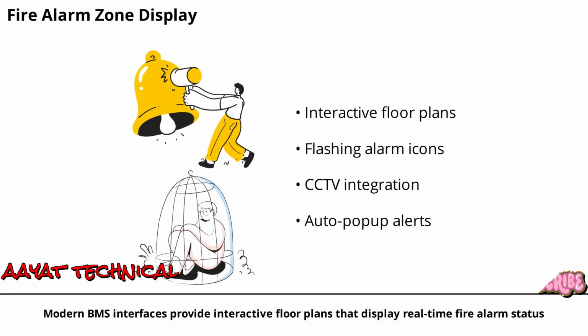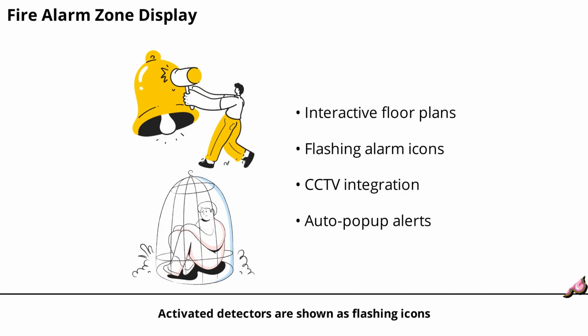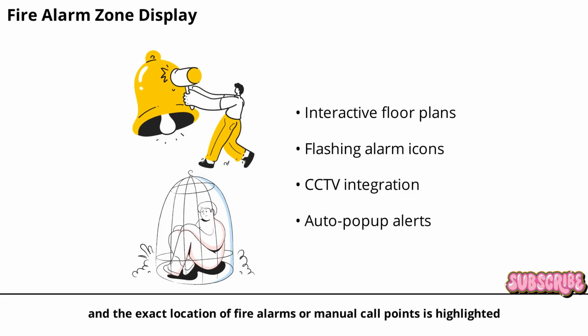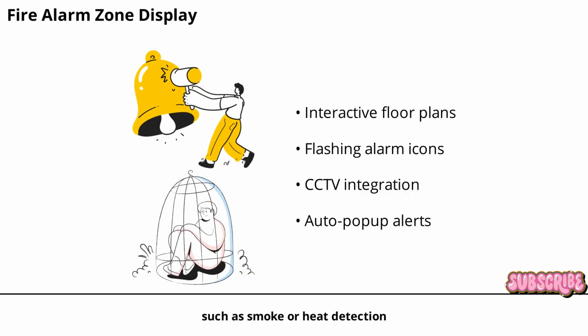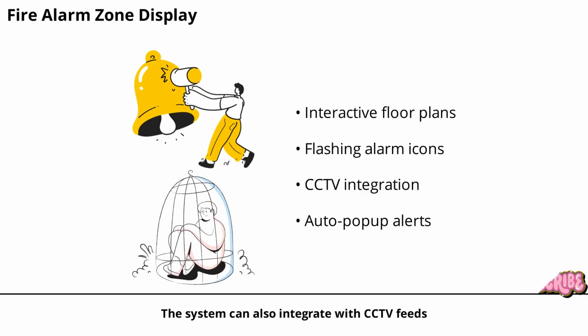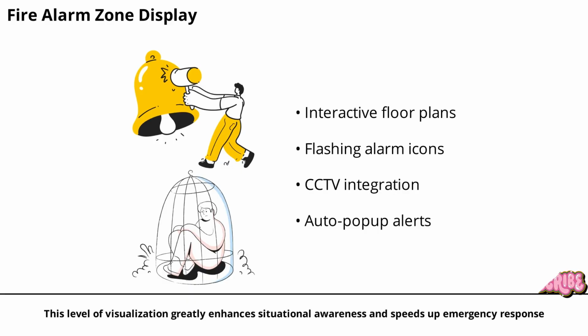Modern BMS interfaces provide interactive floor plans that display real-time fire alarm status. Activated detectors are shown as flashing icons, and the exact location of fire alarms or manual call points is highlighted. Zone-specific alarms, such as smoke or heat detection, are clearly marked. The system can also integrate with CCTV feeds, giving operators visual confirmation of the situation. For critical alarms, the BMS GUI auto-populates alerts with sound, ensuring immediate attention. This level of visualization greatly enhances situational awareness and speeds up emergency response.